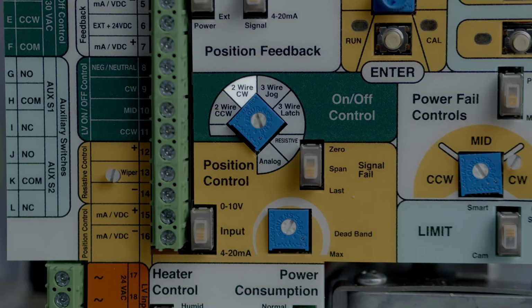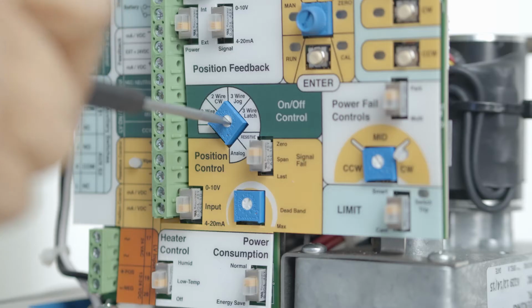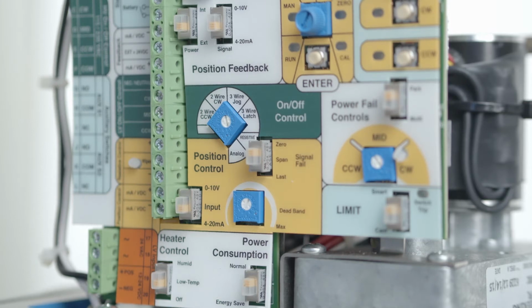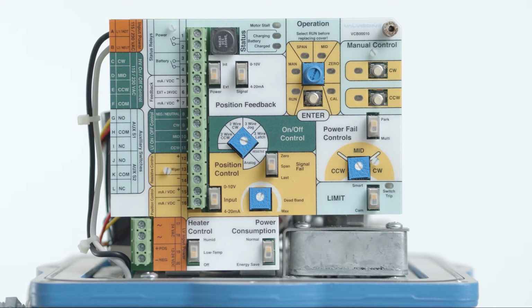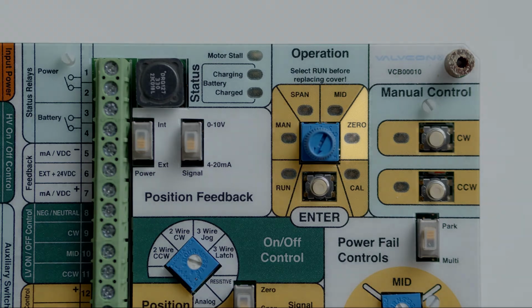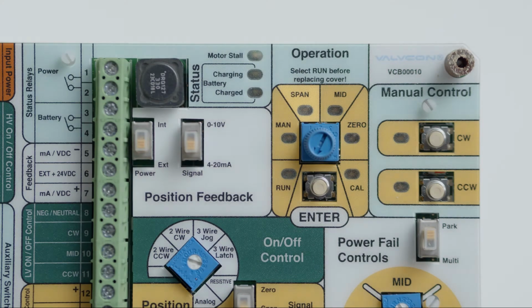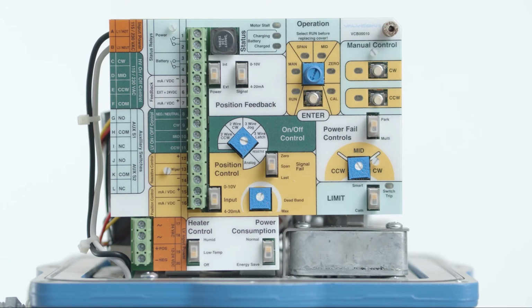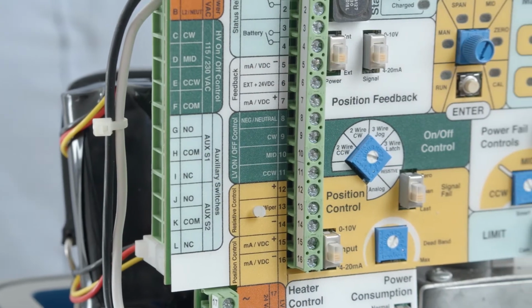Next, select control method: 2-wire CCW, 2-wire CW, 3-wire jog, or 3-wire latch, resistive or analog, by turning the mode selection potentiometer with a small flat blade screwdriver. Field installation of the universal control board or replacement of the feedback potentiometer requires calibration of the potentiometer prior to setting positions and values for 0, mid, and span. Universal control boards installed at the factory are fully calibrated at the factory and should not require further calibration. However, the factory preset calibration may not match the device that the actuator is controlling. Therefore, you may need to recalibrate the actuator to fine-tune it for the application.